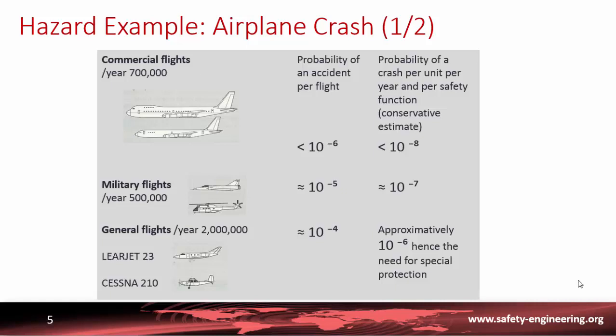General flights are on the order of several million a year, and the probability of accident per flight is also ten times more than for military flights. So the approximate probability of a crash reaching a safety function is on the order of 10^-6. Therefore, the design of nuclear plants must consider this kind of airplane crash.